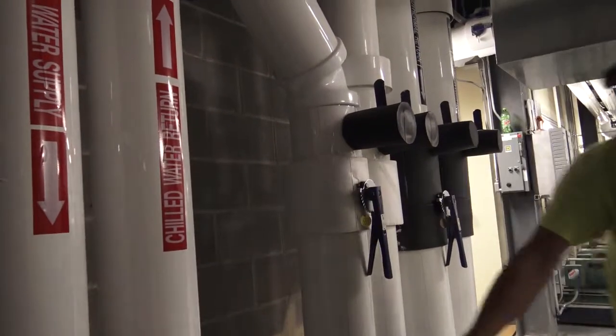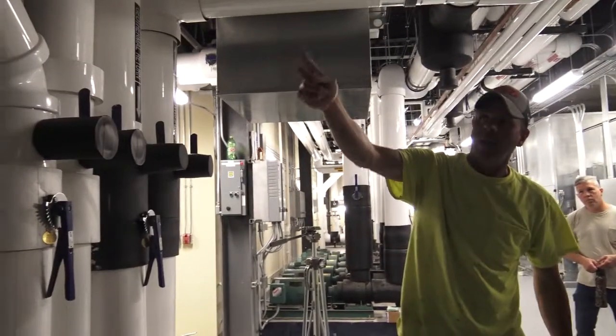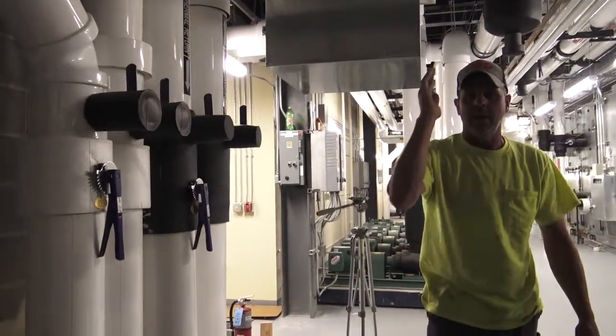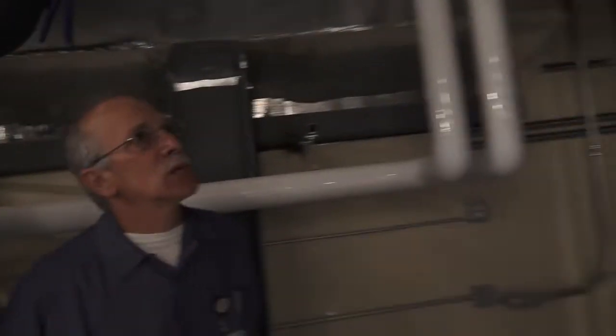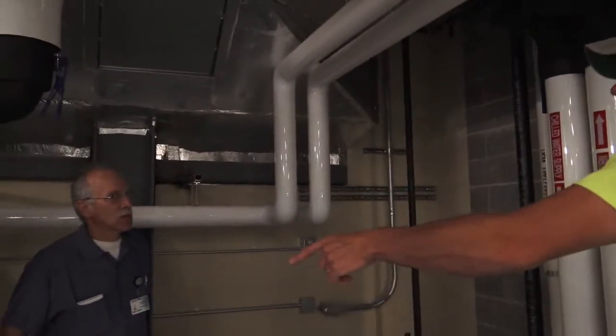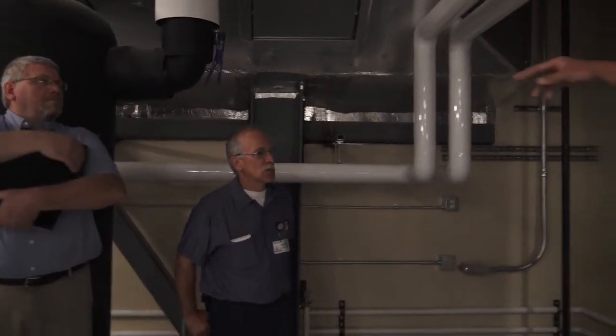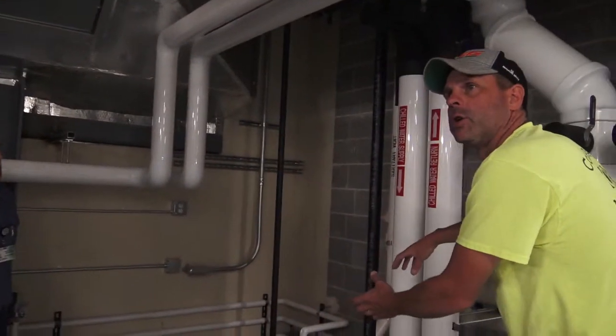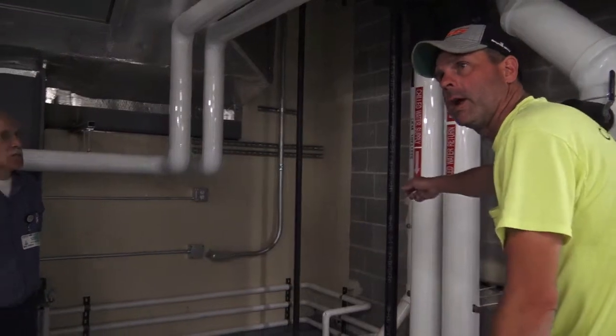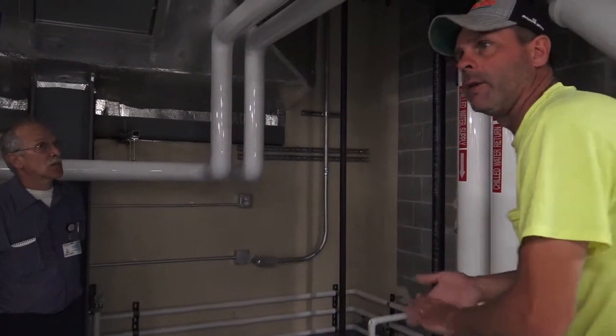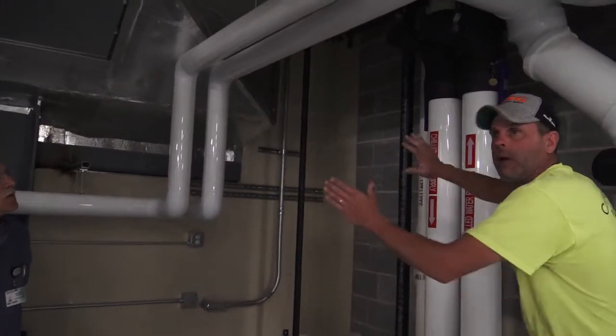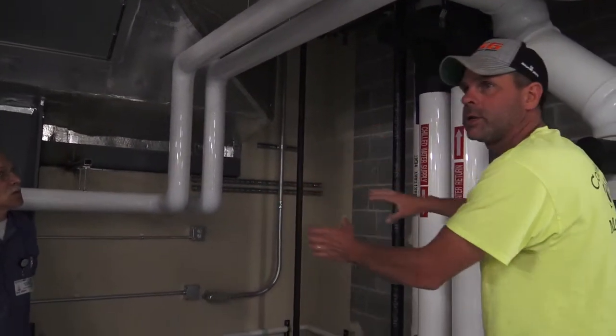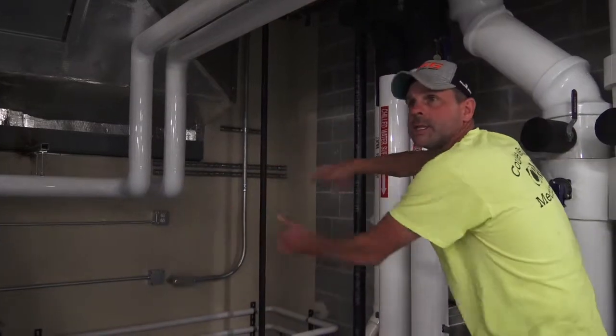These are chilled water return. If you shut these off right here, right now, they go down and run halfway, splitting the building in half. They run down and pick up a blower coil on second, turn, go down a chase, and then go to your LINAC, your linear accelerator, to the blower coils and everything. These are the valves that'll kill that. All your chilled water, all the stuff you've got with chilled water is on this side of the building. There is nothing over there, nothing.